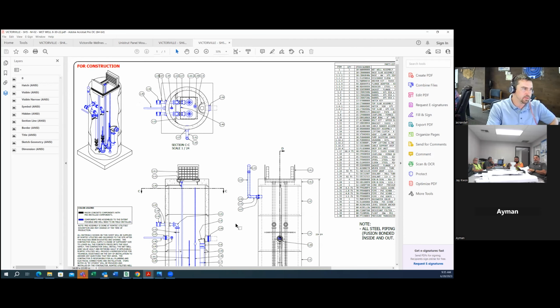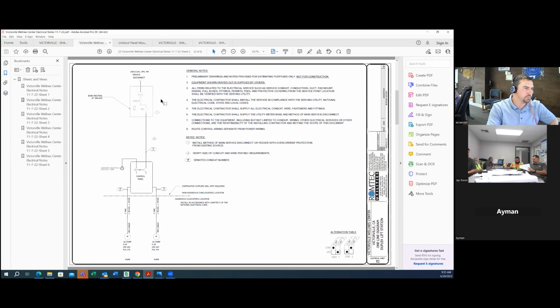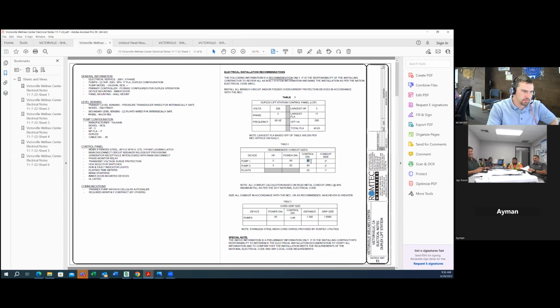I appreciate that. Do we know what size cable and conductors we're pulling for each of those? Yeah, so the pumps are about 1/2 inch diameter or so. I think these pumps have 2 different cables coming off of them. One of them is power, one of them is sensors in the pump, the seals, and I forget the other one. But it looks like 0.85 inches plus another 0.5 inches. And based on the recommended table, 2-inch conduit. So they're kind of all tied together. So you'll be pulling essentially one big cable. This is in our submittal. If you don't have it, I can send it off. Okay, no, I do have it. Okay. Did Victorville have your system before, right?